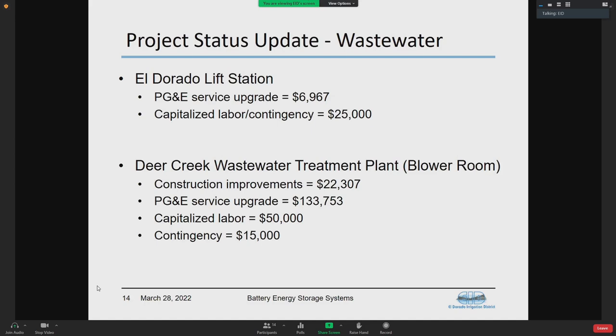The second, larger project is at our Deer Creek wastewater treatment plant, involving a couple of upgrades. First, construction improvements for $22,000: we're going to automate some of the breakers from our new solar facilities. Typically during a power outage, if you're just connected to solar, it shuts off immediately because you can't backfeed into PG&E's lines. This will allow us to automate a portion of the field to go directly into the battery during outages, so we can continue to generate and use that energy during an extended outage.